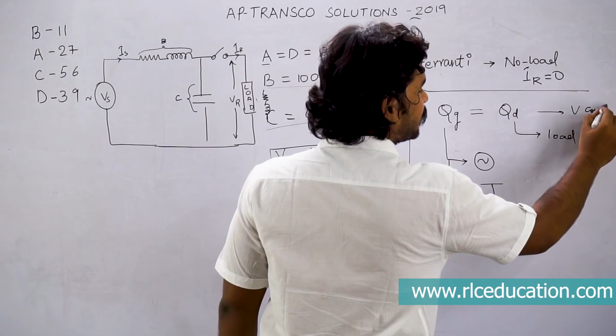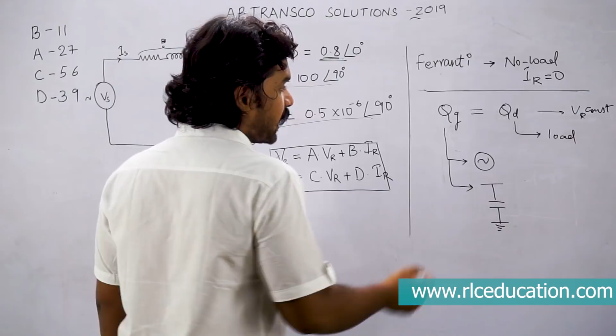As I constantly tell in my crash course videos on YouTube, when reactive power generation equals reactive power demand, the voltage of the system remains constant, or strictly speaking, the receiving end voltage remains constant. But if reactive power generation is more than reactive power demand, the receiving end voltage will rise.